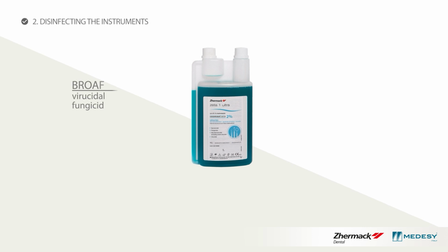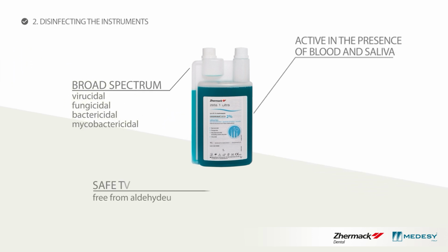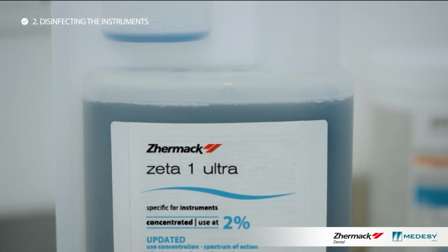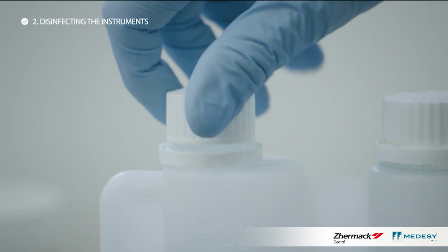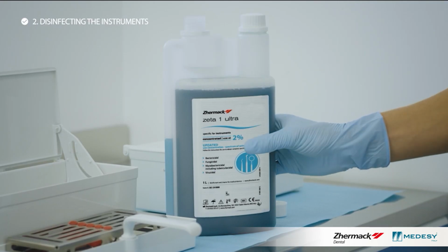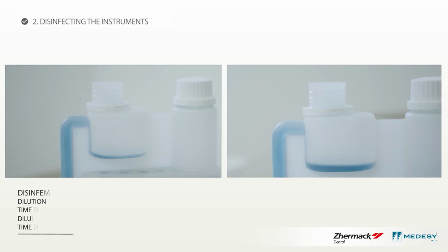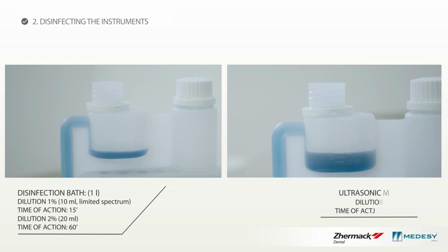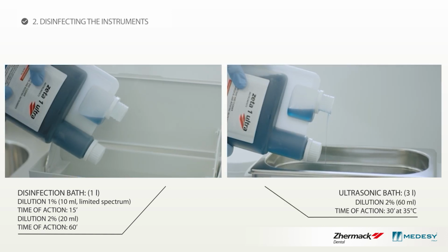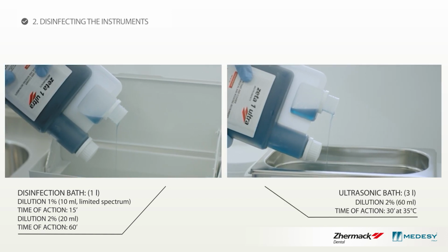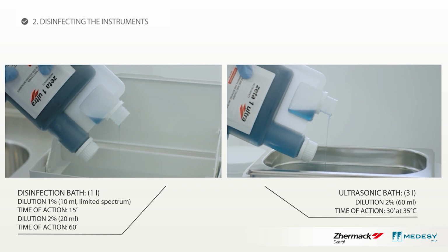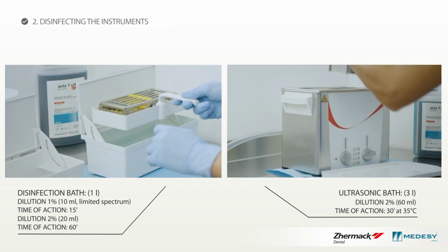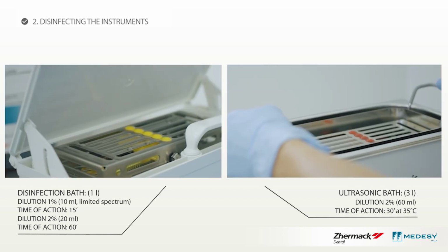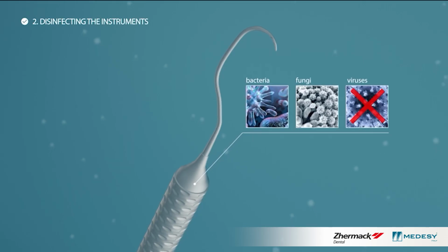Before washing, the instruments must be disinfected by immersing them in a broad-spectrum liquid disinfectant active in the presence of organic residues. The disinfectant solution must be prepared following the manufacturer's instructions scrupulously, respecting the dilution percentages and immersion times indicated to make sure disinfection is effective and avoid damaging or corroding the instruments. The instruments must be fully immersed in the disinfection bath.